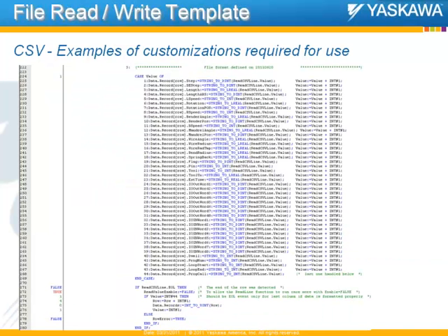So this represents a case statement where each of those 44 columns is read and converted from the string data, the CSV data, into the actual data type of the structure to be used in the IEC application. So you can see down the center here a bunch of string to LReal or string to DINT conversions of the CSV's value as we parse through the file.